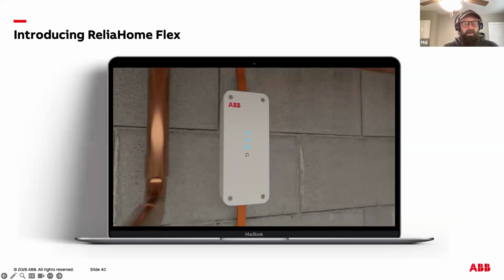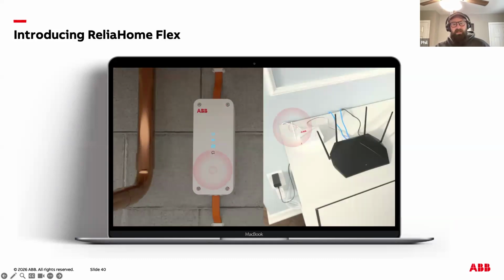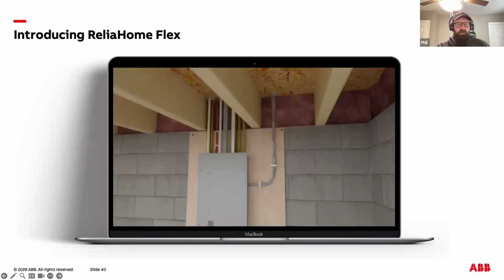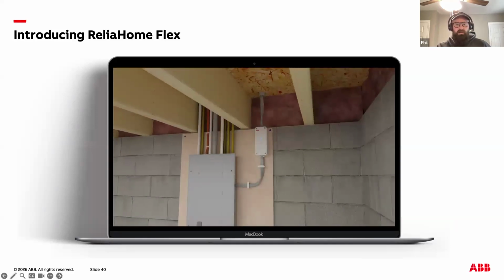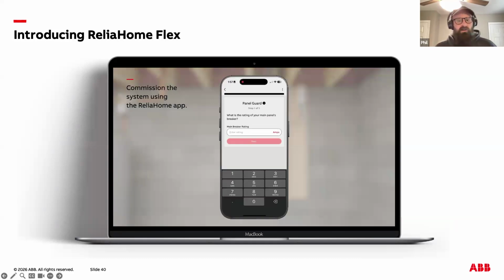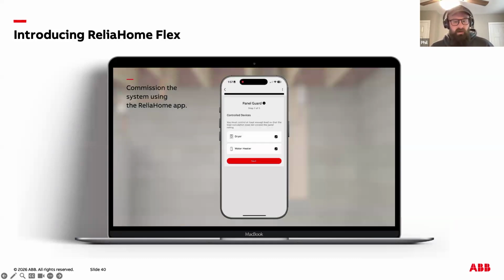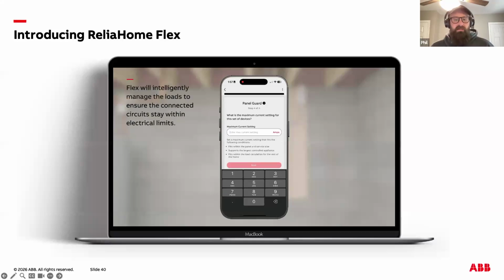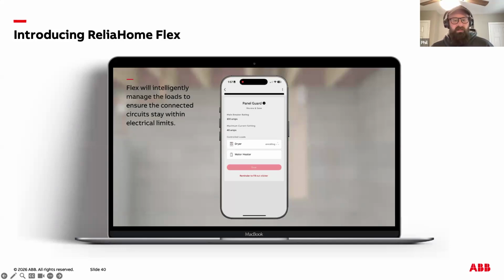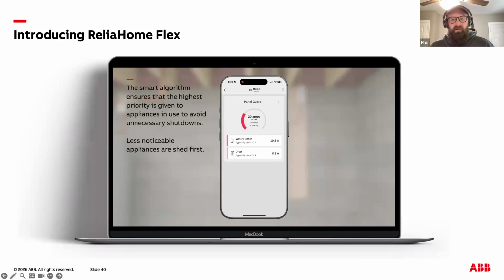Commissioning is done via our ReliaHome app. Flex intelligently manages loads to ensure the connected circuits stay within the electrical limits. Similar to our grouped monitoring example from 120.7, our smart algorithm ensures that the highest priority is given to in-use appliances to avoid unnecessary shutdowns. Less noticeable appliances are always shed first.